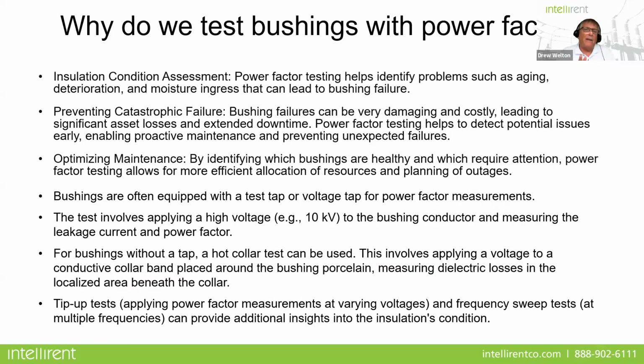But why do we test bushings with power factor? Well, we want to look at the insulation condition assessment. Power factor testing will help identify things such as aging, deterioration, moisture ingress, or anything that can lead to bushing failure. And this, of course, will help prevent catastrophic failure. We know that bushing failures can be damaging and costly, obviously. Then there's optimizing maintenance. By identifying which bushings are healthy and which require attention, power factor tests allow for more efficient allocation of resources and planning of outages.